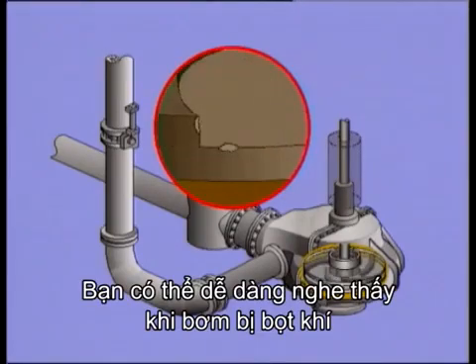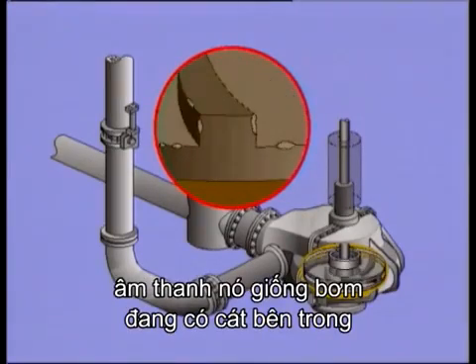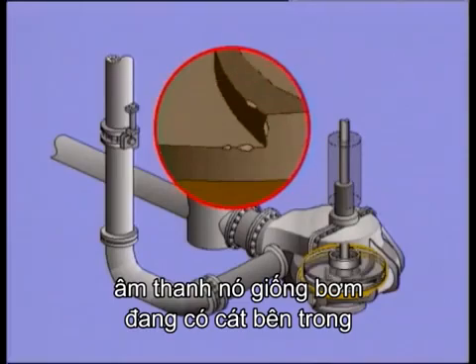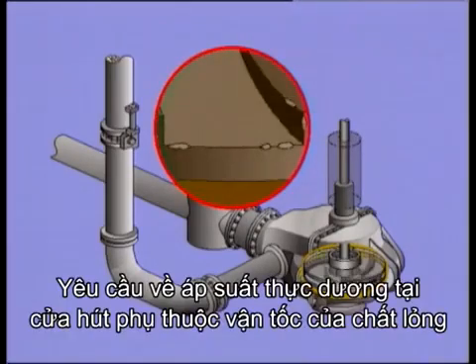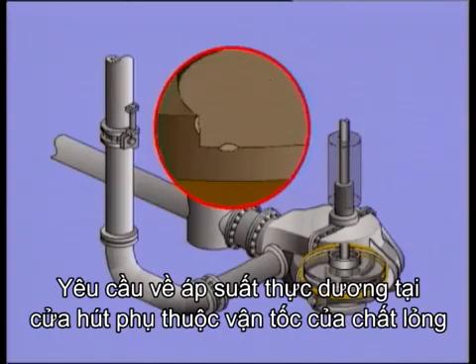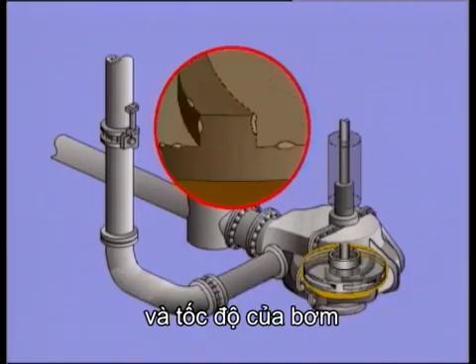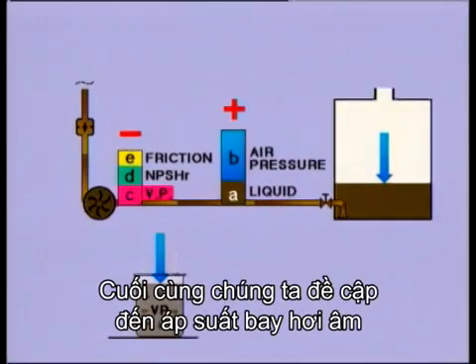You can easily hear when a pump cavitates. It sounds like you're pumping gravel. Net positive suction head required is dependent on the velocity of the liquid and the speed of the pump. The last minus is the vapour pressure.